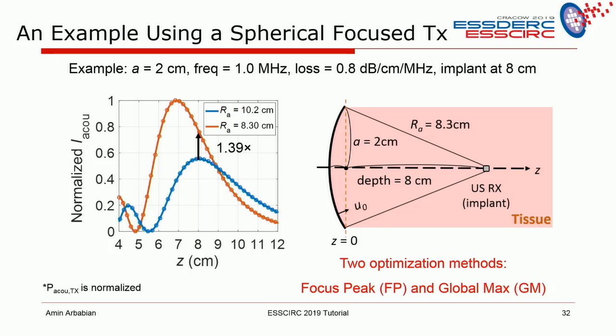Option number two is to focus slightly inward. Now remember, when you focus a little slightly inward, your focusing efficiency gets better. Your grain of rice gets smaller. So even though you're not at the peak, the actual power you receive at that focal point is still higher. Right? Does that make sense? Hopefully this makes sense. So I'm focusing now at 7 centimeters instead of 8, but the focus I get at 8 centimeters is still better than the 7.